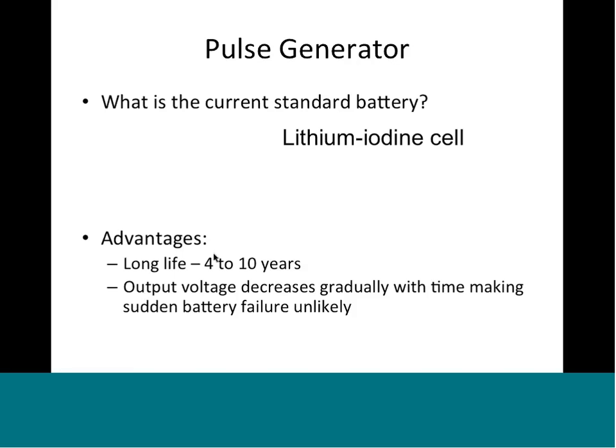When you're running out of battery, unlike a battery in your clock where it runs out and stops working, you can't afford that with a pacemaker. Therefore the output voltage will gradually decrease over time - you won't get a sudden failure making it an emergency. As long as you're checking the pacemaker at certain intervals, you'll see the output is decreasing, the battery life is going down, and it gives you time to plan a battery replacement.